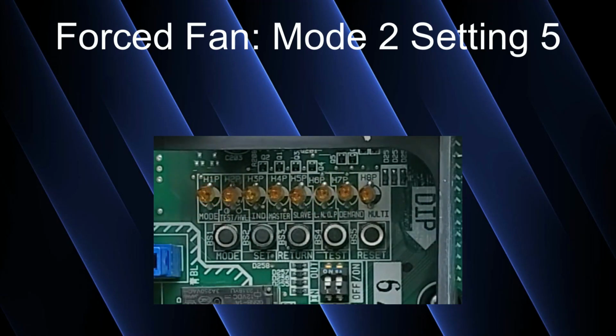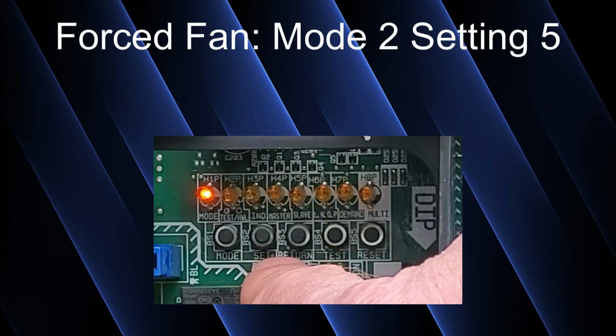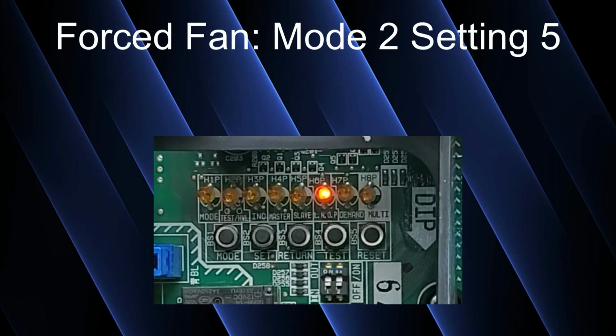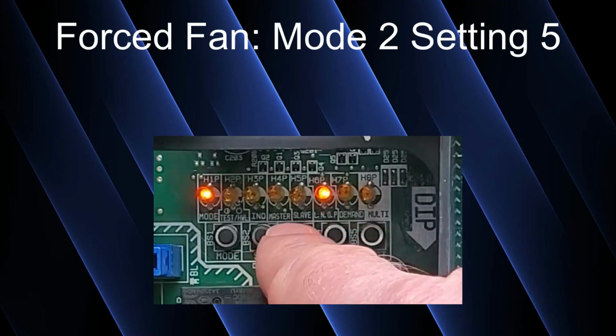So now H6P will be blinking. You save this setting by pressing return 1 time. It goes from a flashing 6 to a solid on 6. That tells you you've saved that setting. And now you need to activate that setting. So you press return 1 more time and it goes back to H1P solid by itself.